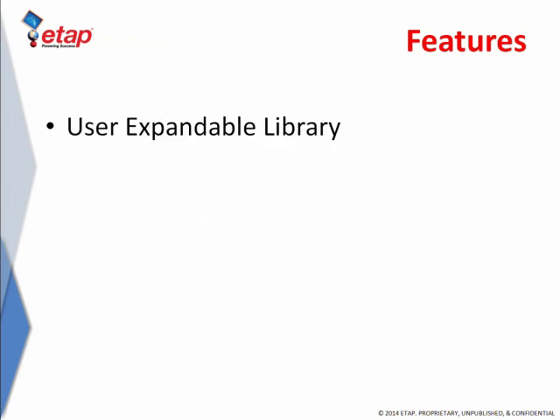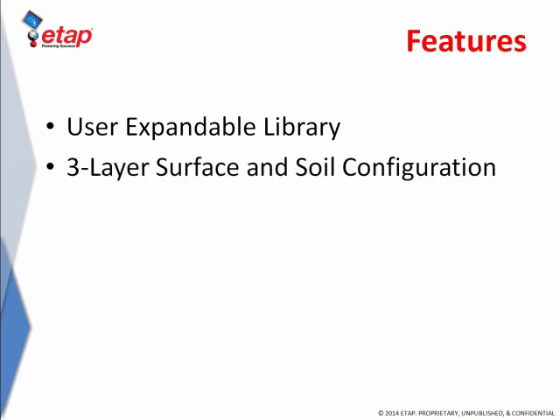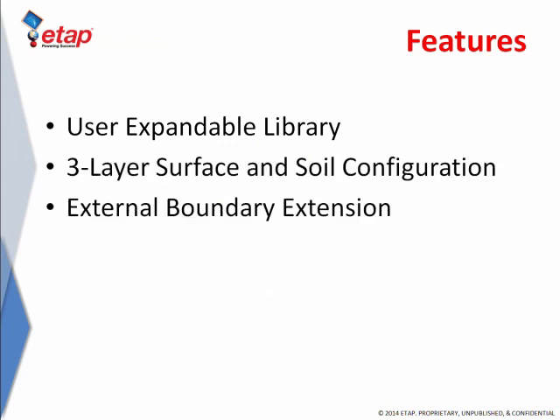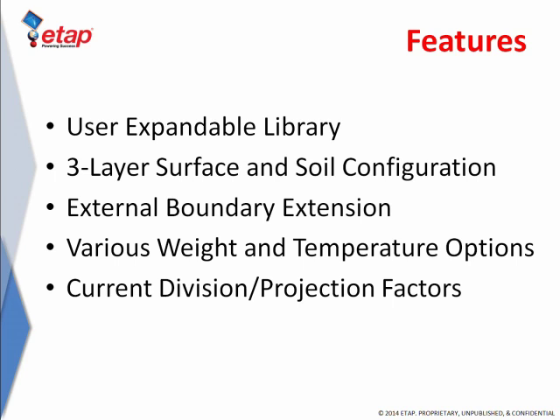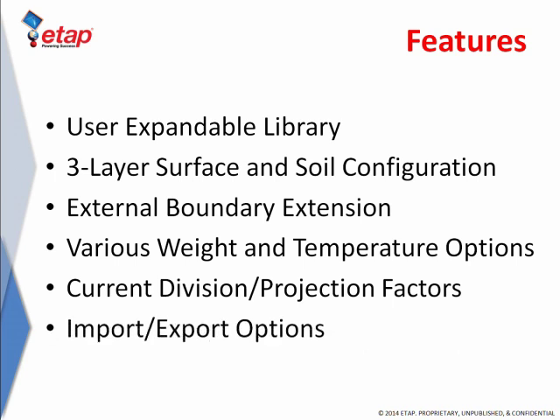There are quite a few other features provided by the ETAP ground grid module, including an extensive user expandable library, a three-layer surface material and soil configuration, and allowing for extended boundaries. This module considers workers' weight, ambient temperature, current division and projection factors, and has the capability to import your designs from AutoCAD and export the results to a desired document format.